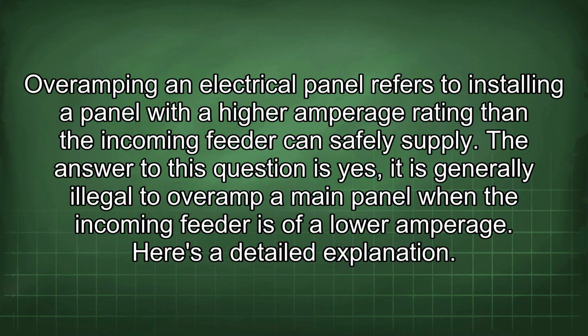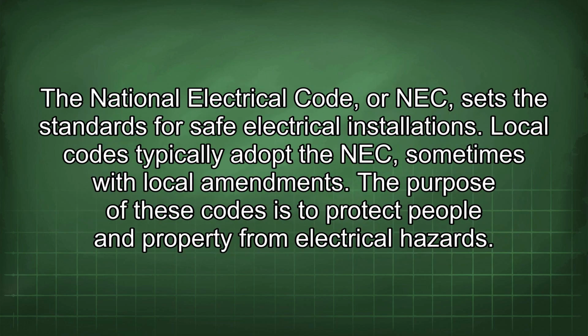Overamping an electrical panel refers to installing a panel with a higher amperage rating than the incoming feeder can safely supply. The answer to this question is yes, it is generally illegal to overamp a main panel when the incoming feeder is of a lower amperage. Here's a detailed explanation. The National Electrical Code, or NEC, sets the standards for safe electrical installations. Local codes typically adopt the NEC, sometimes with local amendments. The purpose of these codes is to protect people and property from electrical hazards.